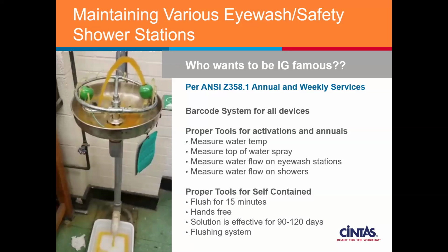The second part of an effective program is having the proper tools in place for employees to do any activations or maintenance. When I meet with customers, one of the first questions I like to ask is: when you last did your annual inspection on this device, what was the temperature of the water? I ask that because if they're following the ANSI standard, that's a detail they should truly know. Unfortunately, I typically get one of two answers: 'I'm really not sure' or 'we don't actually do that.' That tells me that even though you want to follow the ANSI Z358 standards, you haven't equipped your employees with the tools to do that job effectively.